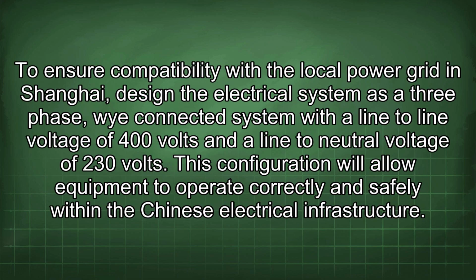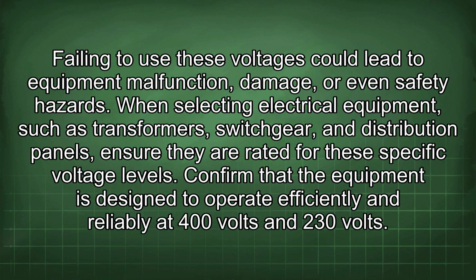To ensure compatibility with the local power grid in Shanghai, design the electrical system as a three-phase, Y-connected system with a line-to-line voltage of 400 volts and a line-to-neutral voltage of 230 volts. This configuration will allow equipment to operate correctly and safely within the Chinese electrical infrastructure. Failing to use these voltages could lead to equipment malfunction, damage, or even safety hazards.